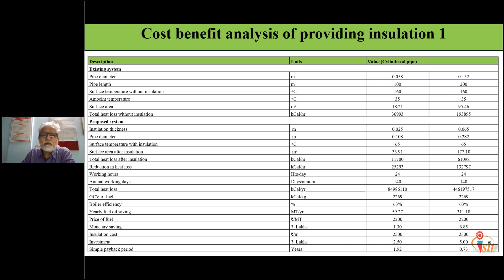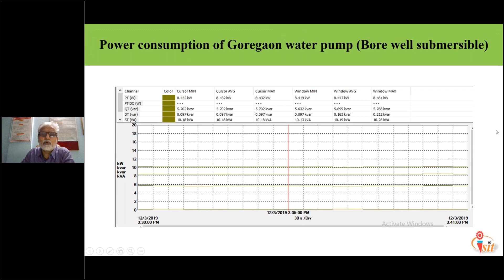Here is another example, of a submersible pump used in a bore well. This submersible pump consumes around 11.29 kilowatts for that particular application. The bore well, from where they lift water, is around 6 kilometers from the college campus. They have two 10 HP pumps, one drawing 10.29 kilowatts and another consuming 8.447 kilowatts. One pump is old, the other is new, and both work for 12 hours. Based on this, we recommended a replacement.